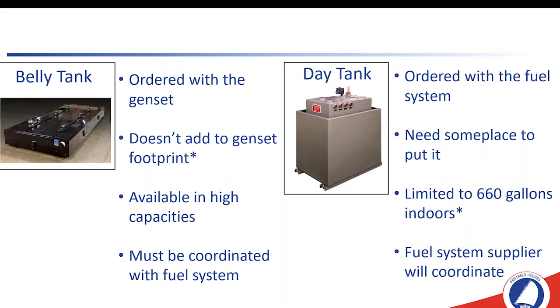It may sound like a small thing, but we have had projects where a contractor provided their own day tank, and some of the switches in the day tank were normally closed in the down position and some were normally open in the down position, and we programmed for all the switches to be closed in the down position, and the pump controls wouldn't work, and nobody on site could figure out that the reason was that some of the float switches were backwards. It's not rocket science, but not everybody has troubleshooting skills.